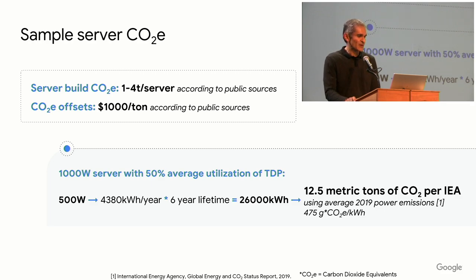Also based on public sources, we know that carbon dioxide offsets are about $1,000 a ton. If that same server consumes 1,000 watts max and 500 watts average over its lifetime, as a sample example, working through a 6-year lifetime, that server would consume 26 megawatt hours, or 26,000 kilowatt hours of power. According to IEA, in a typical data center that would be 12.5 metric tons. Multiplying through by $1,000 to get the carbon dioxide emissions offset, that would be $12,500 for the lifetime of the server to offset the carbon dioxide emissions.